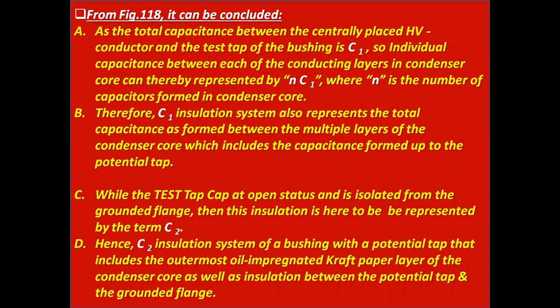From figure 118, it can be concluded, A, as the total capacitance between the centrally placed HV conductor and the test tap of the bushing is C1, the individual capacitance between each of the conducting layers in the condenser core can thereby be represented by NC1, where N is the number of capacitors formed in the condenser core. Therefore, the C1 insulation system also represents the total capacitance formed between the multiple layers of the condenser core, which includes the capacitance formed up to the potential tap.